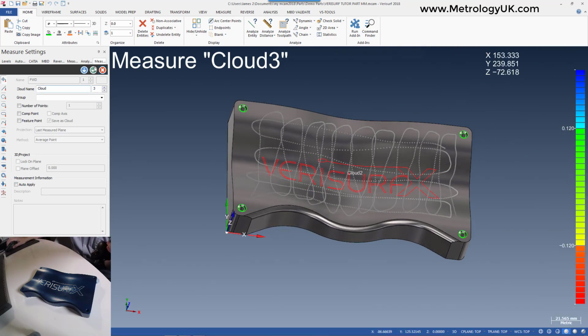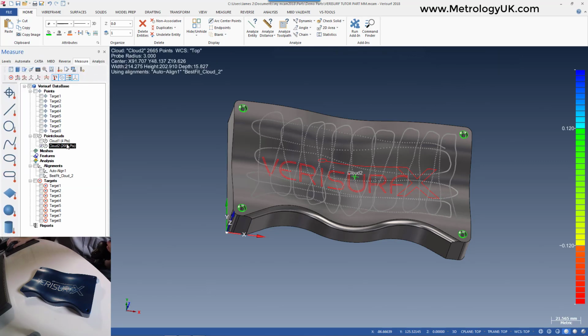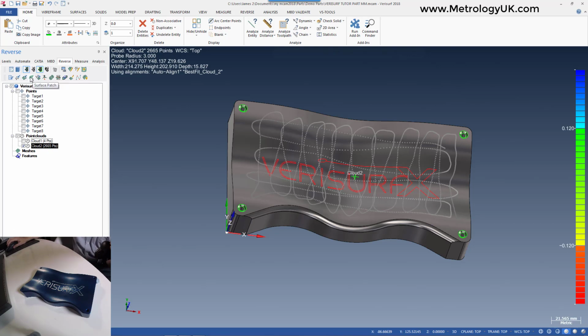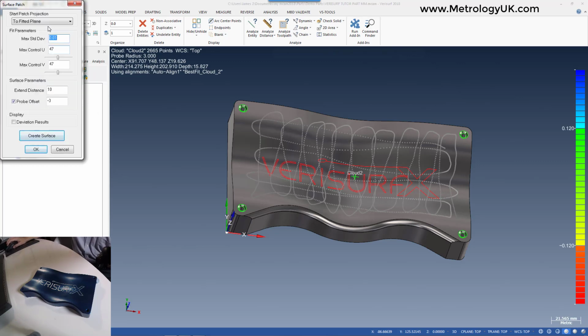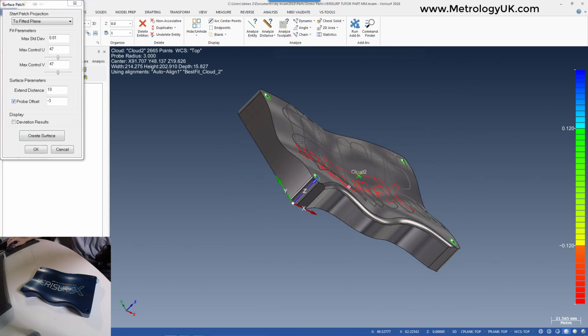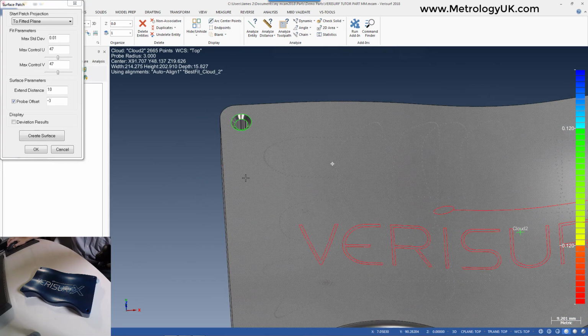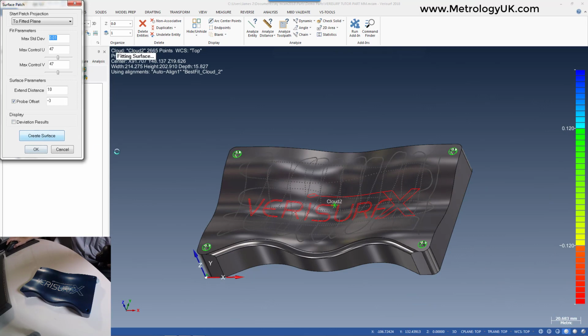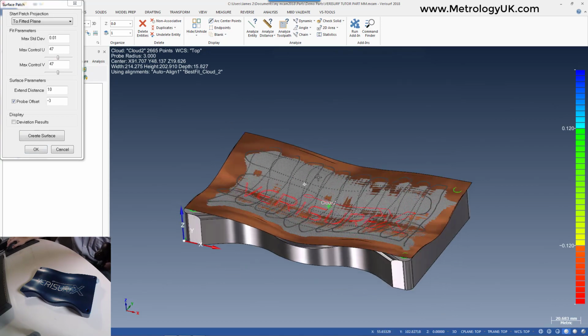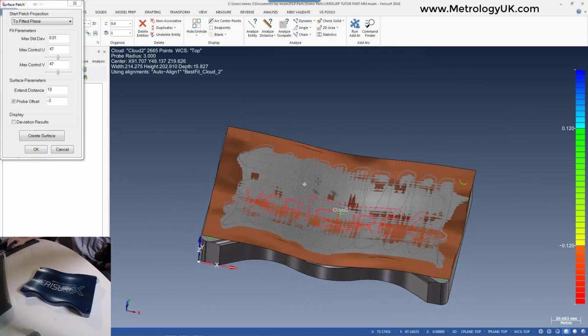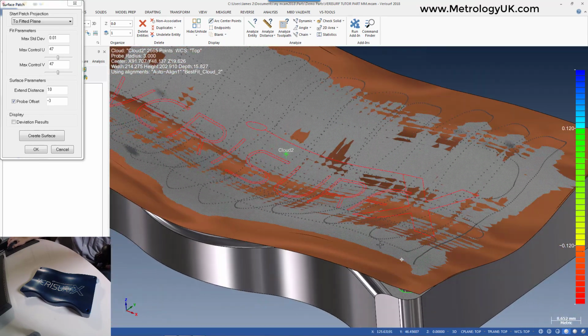Okay, so we've taken a bit of a random sample, not too much data, but it just gives you a bit of an indicator. I'm going to now take that data set into the reverse module and go to surface patch, which is a module that allows us to create lofted style surfaces from just straight point clouds. And we can extend beyond the measurement for modeling purposes, and also offset automatically for the probe radius, because obviously this is probe center data, as you can see. Right, so I'm just going to create the surface. You can improve the accuracy by increasing the UV content. This will make the surface tighter to the original data set, and as you can see, it's recreated the surface and it mimics the original surface, so that just gives you a little bit of an indicator of the accuracy of the process.